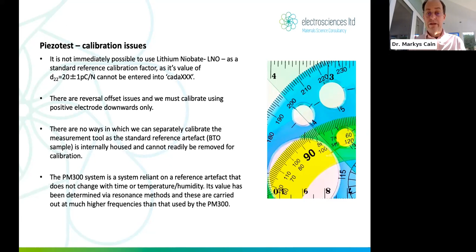It's very difficult in the Piezotest machine, if not almost impossible, okay, to separately calibrate the system because the internal standard reference artifact, which is BTO typically, is internally housed. You can't move it. I mean, you can take it apart. It's all soldered in. It didn't used to be. It used to be brass electrodes and so on, but it's all soldered in now. So it's very difficult to remove, to calibrate exactly, which means you need to use external artifacts which are calibrated in other ways as your calibrant system.